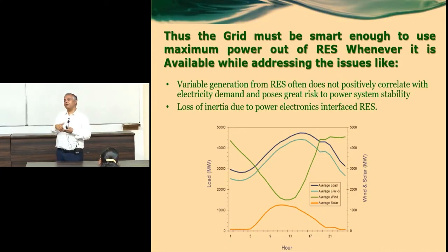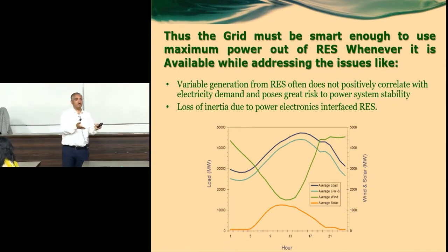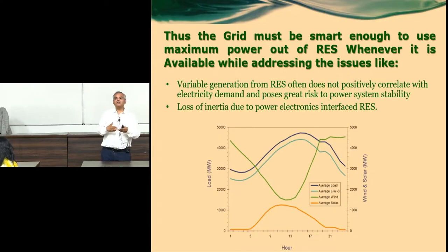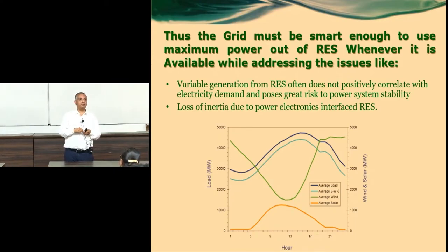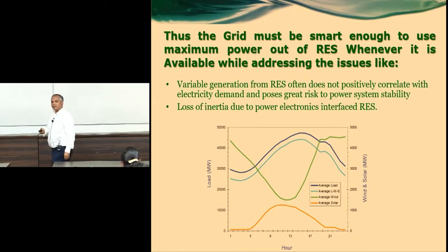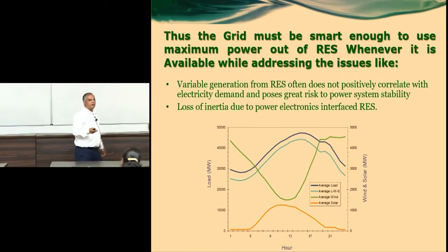But unfortunately, because we are going to introduce more and more renewable energy sources, that half J omega square capacity is not available. To overcome that issue, we are going to have dedicated battery energy storage systems. We call it utility scale energy storage system, megawatt, gigawatt energy storage system. Those facilities have already been installed in Australia, in the US, and in China, and India has also tendered at certain locations to go for that kind of thing.